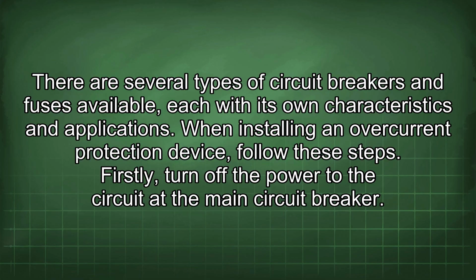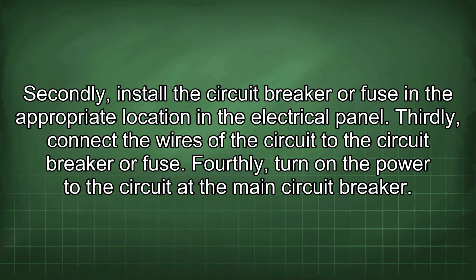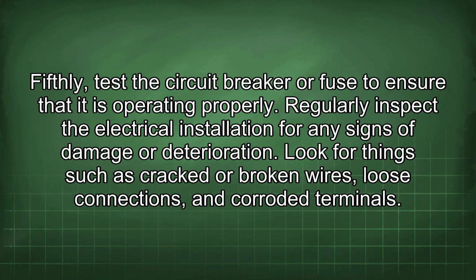When installing an overcurrent protection device, follow these steps. Firstly, turn off the power to the circuit at the main circuit breaker. Secondly, install the circuit breaker or fuse in the appropriate location in the electrical panel. Thirdly, connect the wires of the circuit to the circuit breaker or fuse. Fourthly, turn on the power to the circuit at the main circuit breaker. Fifthly, test the circuit breaker or fuse to ensure that it is operating properly.